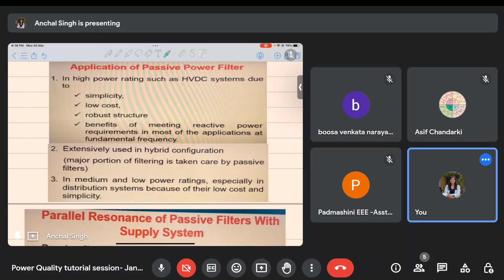And they are extensively used in hybrid configuration. Hybrid configuration became popular because we know we have a need for active compensation, but to save some money, we design a low rating active compensator, and the rest is compensated by passive filters. So this hybrid configuration is very extensively used.